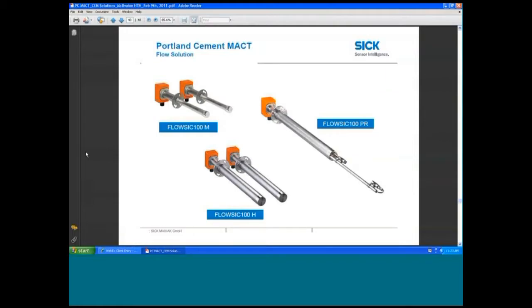The two other measurement requirements, flow I mentioned as a secondary requirement for PM CEMS and mercury. We would generally recommend the ultrasonic flow technology for monitoring of the flow. There's various different types depending on the application, depending on the duct size, the dust concentration. If you didn't have access to both sides of a stack or were trying to replace something like a pitot tube, you could go with a probe style ultrasonic to accomplish that. Next slide.